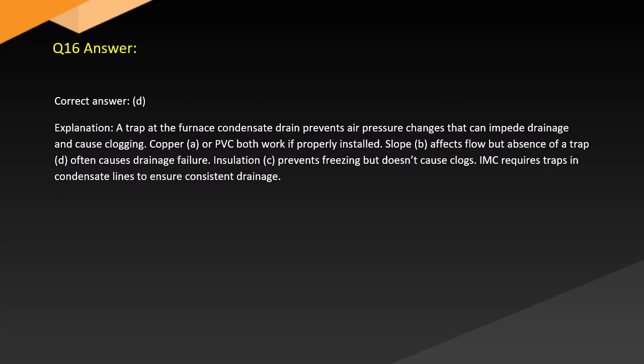Answer. Correct answer: D. Explanation: A trap at the furnace condensate drain prevents air pressure changes that can impede drainage and cause clogging. Copper (A) or PVC both work if properly installed. Slope (B) affects flow, but the absence of a trap (D) often causes drainage failure. Insulation (C) prevents freezing but doesn't cause clogs. The IMC requires traps in condensate lines to ensure consistent drainage.